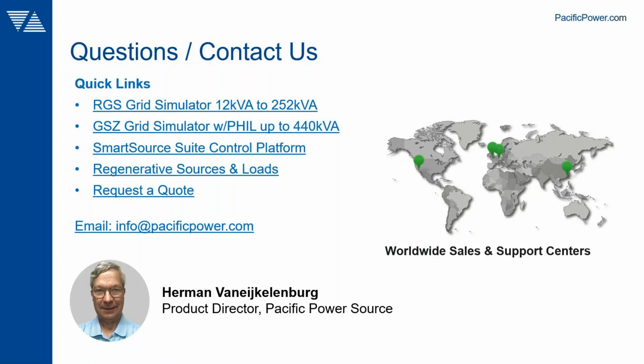Can I parallel two or more grid simulators to get a high power system that don't have the same model and power rating? You can if they are the same series. So if they are both RGSs, then yes. Let's say you have a 12 kilowatt and a 21 kilowatt, you can parallel those and end up with the sum of the two, so 33 kilowatt. They don't have to be the same power level. Generally customers order larger systems using the larger of the two and parallel the same power level to get higher power with fewer units, but it's not strictly mandatory. If you have multiple units bought at different times at different power levels, as long as they're the same series, you can parallel them. Yes.